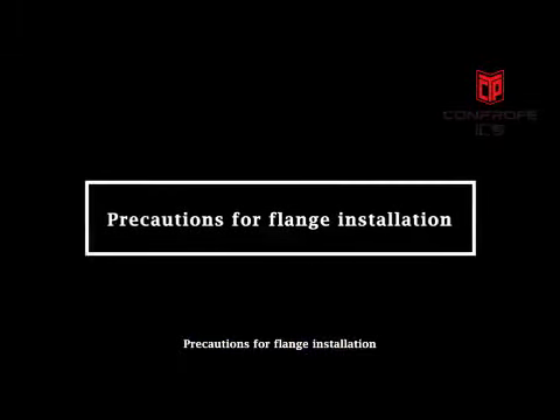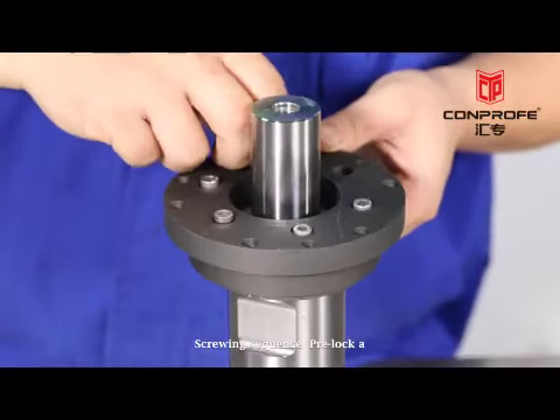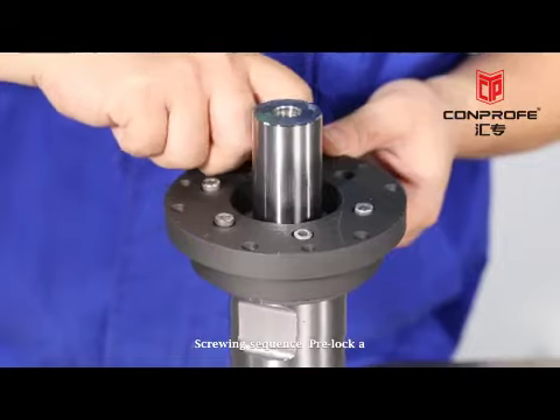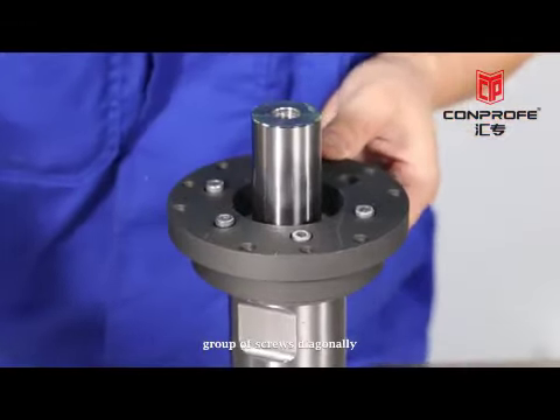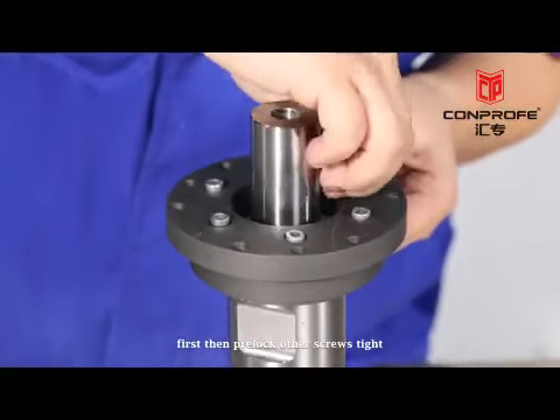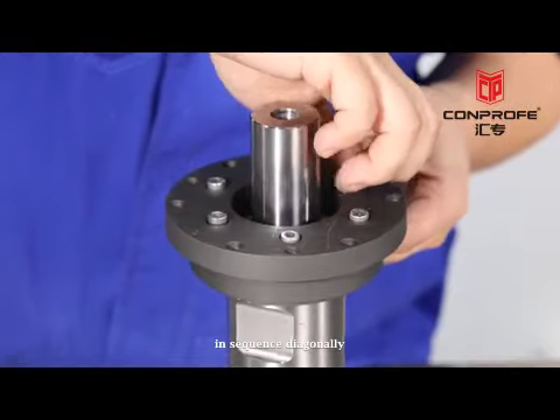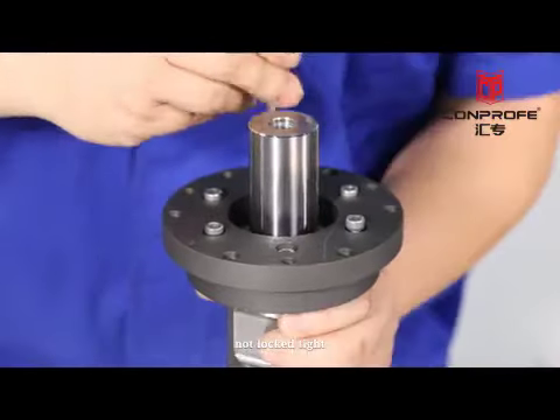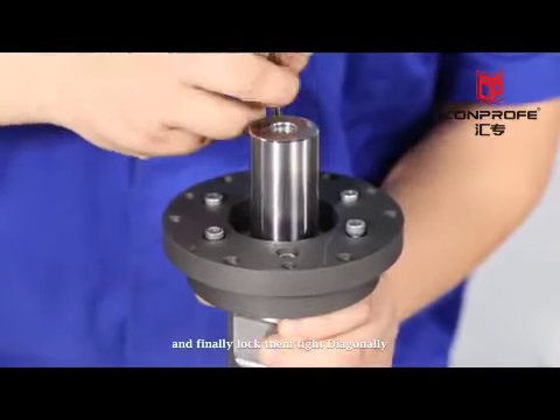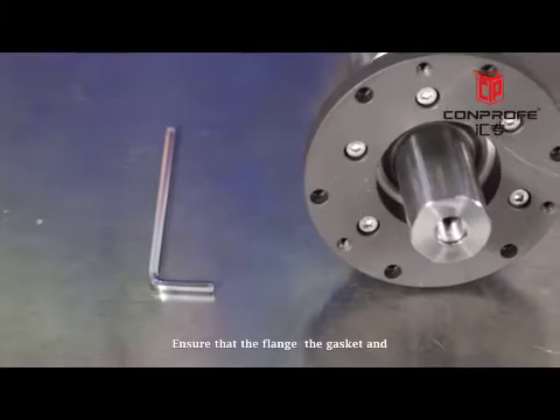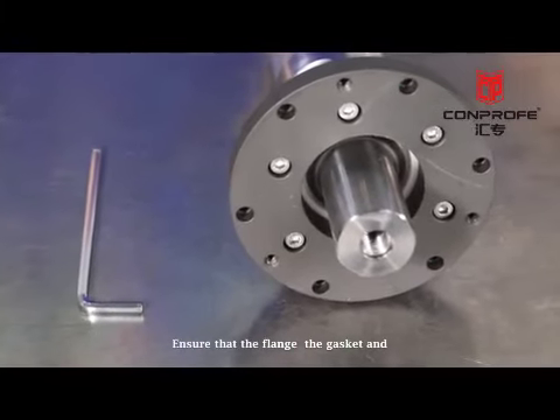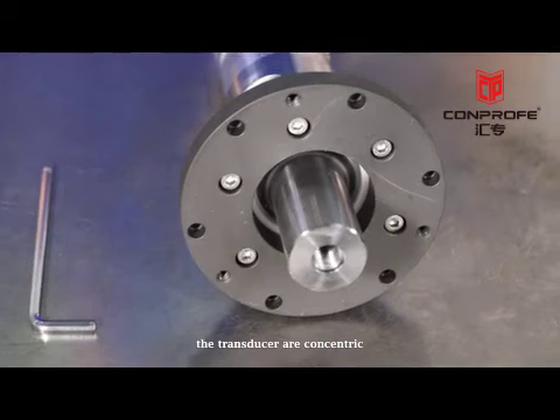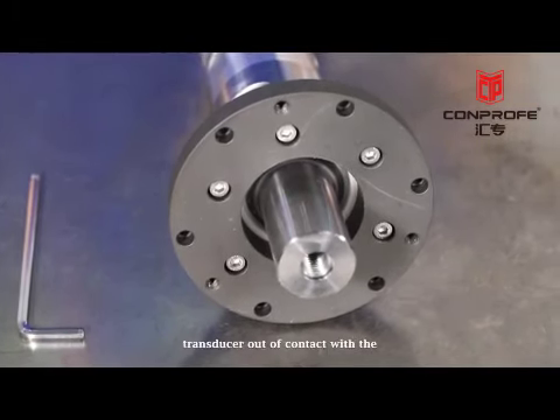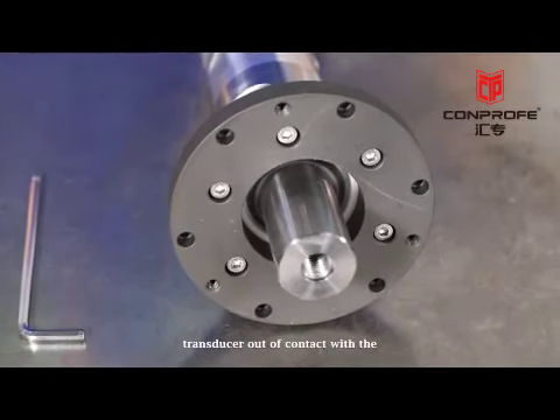Precautions for flange installation. Screwing sequence. Pre-lock a group of screws diagonally first, then pre-lock other screws tight in sequence diagonally, not lock tight. And finally lock them tight diagonally. Ensure that the flange, the gasket, and the transducer are concentric. Keep the rest parts of the transducer out of contact with the flange except the edge.